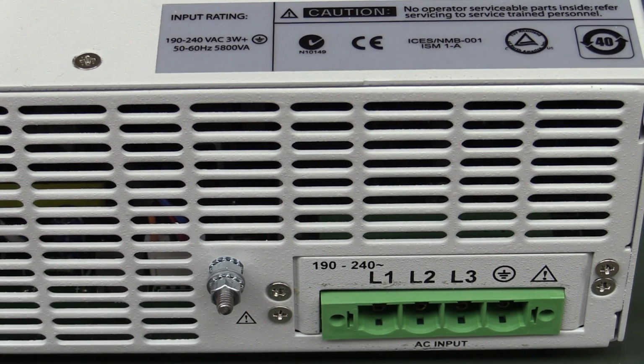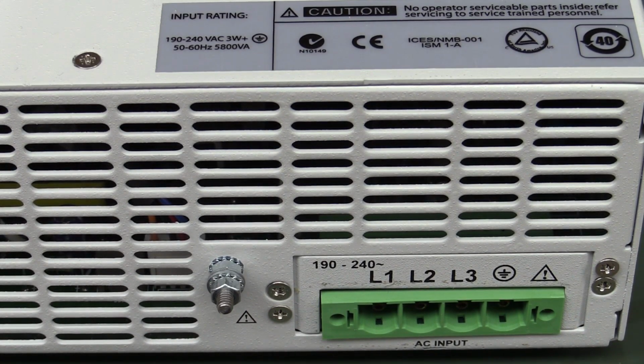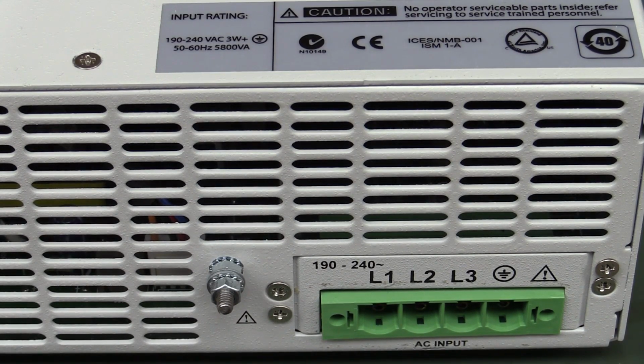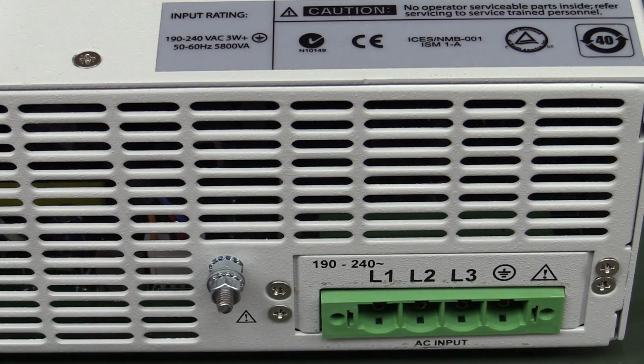Wrong. This one's actually a 120 volt US model because we're talking 3-phase, and in a Y arrangement, that can be 208 volts, or it can be 240 volts, depending on the particular configuration per phase for a 120 volt nominal country like in the US. There are various standards, and I won't go into them. It depends on what type of factory and installation and what type of 3-phase system, how it's wired, etc., etc.